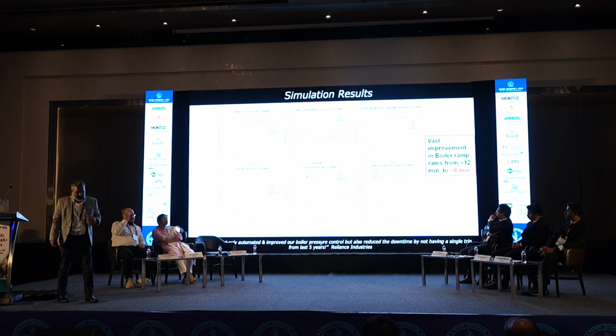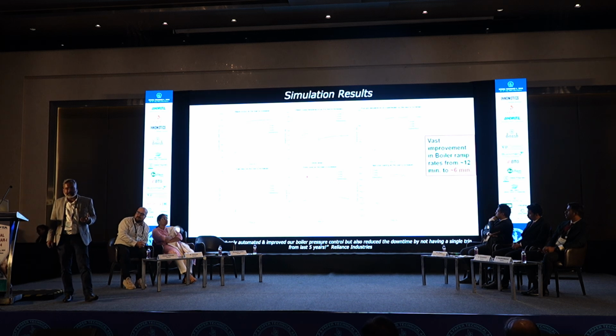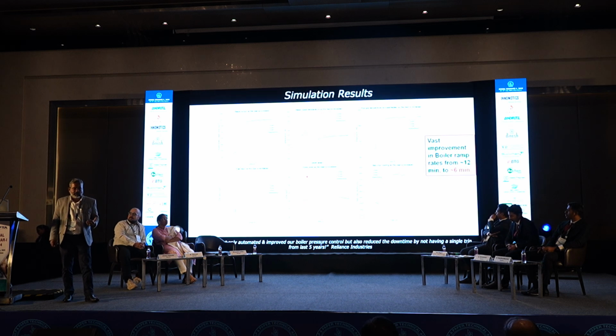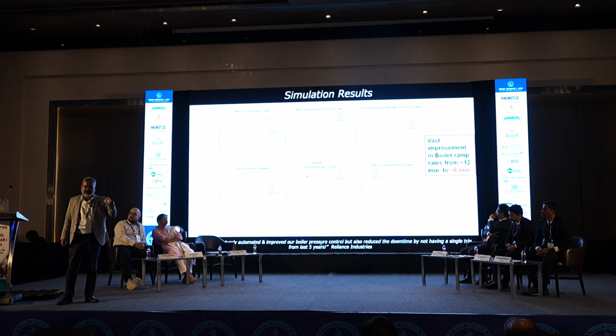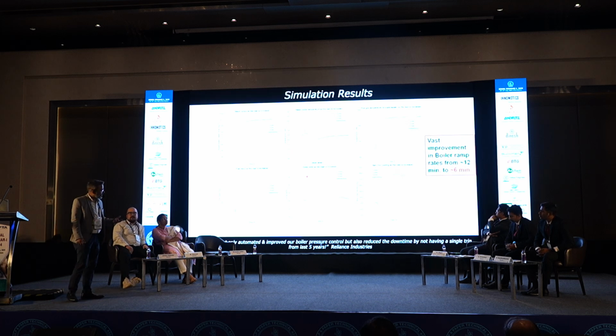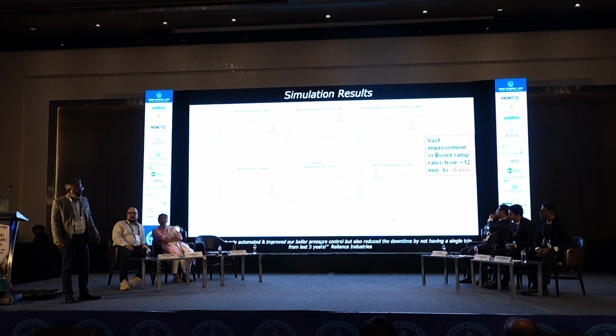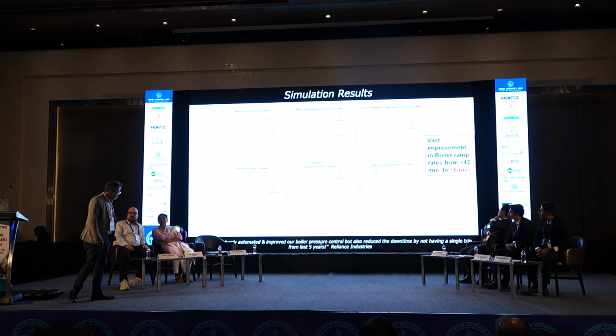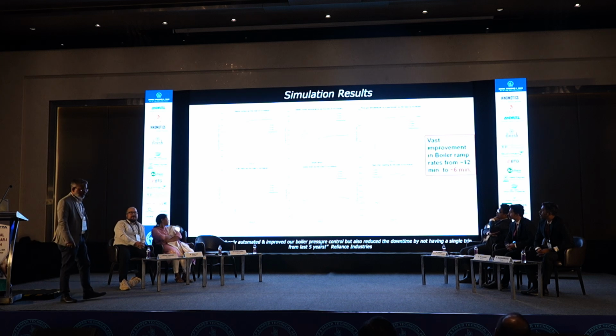So one major achievement from this particular project was that the boiler ramp rates were very well improved. It has come down from 12 minutes to 6 minutes. So boilers were pretty well tuned, the logics were working perfectly fine, their PID parameters were tuned. Some master header controllers have been deployed there, and this is the feedback that we got. It is visible that their plant has been running for the last 5 years without a single trip.